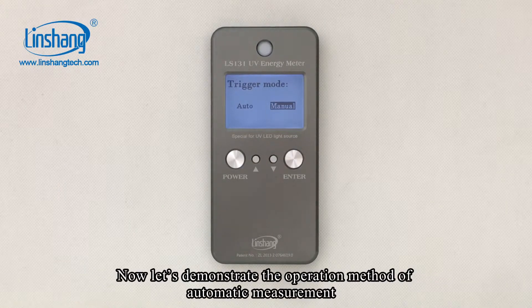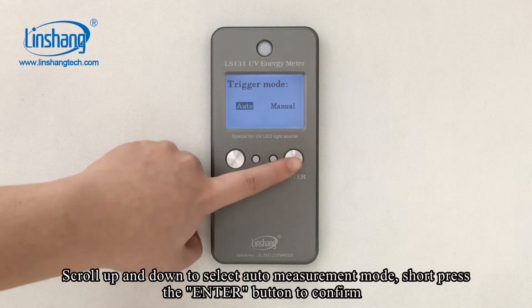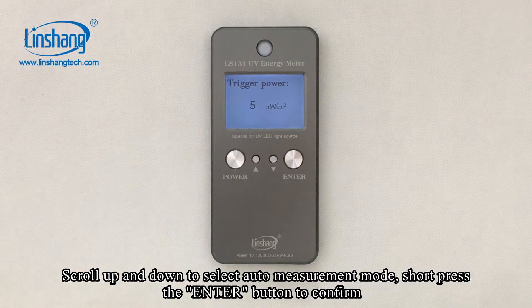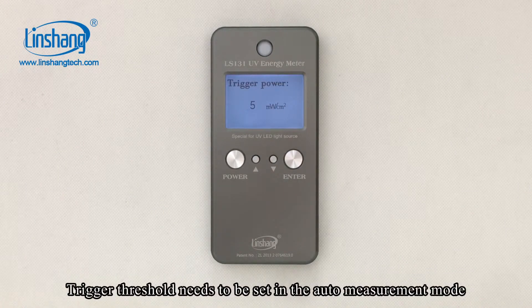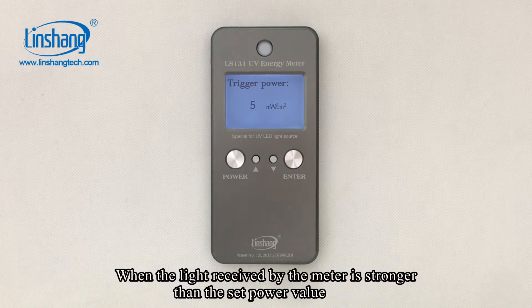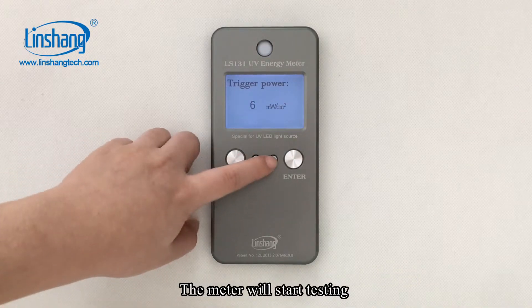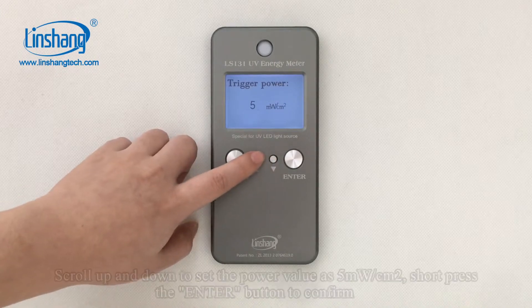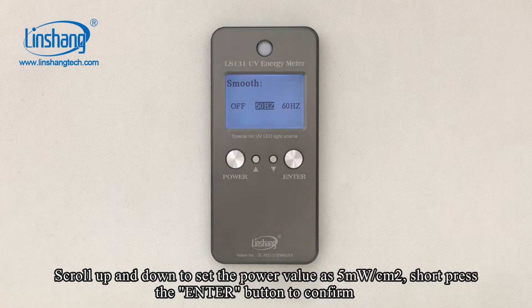Now let's demonstrate the automatic measurement. Scroll up and down to select the measurement mode, then short press the ENTER button to confirm. In the automatic mode, a trigger threshold needs to be set. When the light received by the meter is stronger than the set power value, the meter will start testing. Scroll up and down to set the power value, then short press the ENTER button to confirm.